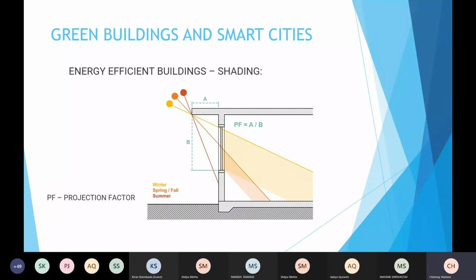Shading can make a huge impact. You can have a south or west facing window, but with proper shading design, the heat coming in can be the same as through a north-facing or shaded window. Shading design is itself a huge subject, because you want light during winters but not heat from the sun during summers. Complex simulations and calculations determine the size of the shading projection, A, as a function of the window height, B - called the projection factor. These calculations need to be done for all new buildings, but unfortunately they're the most neglected aspect.